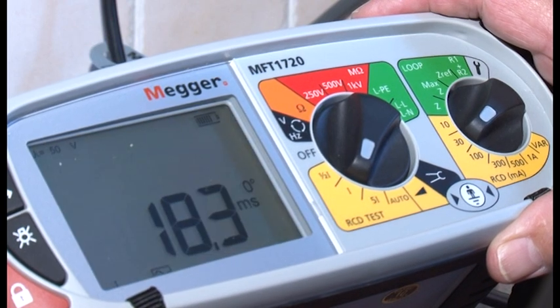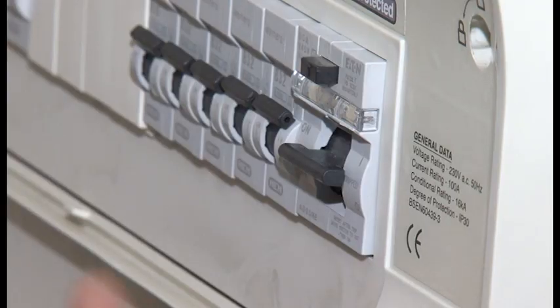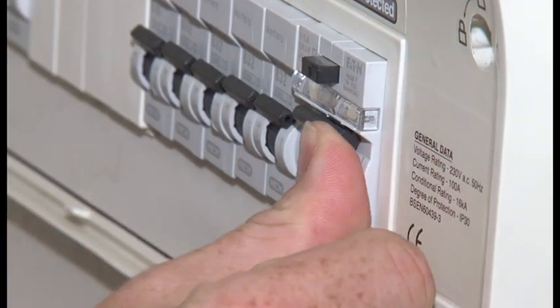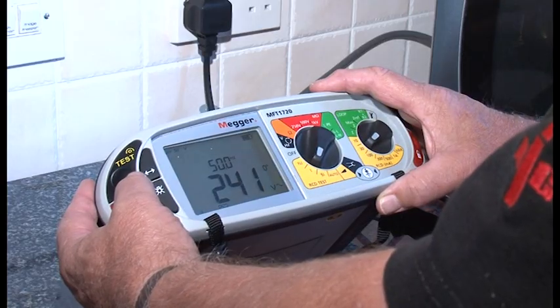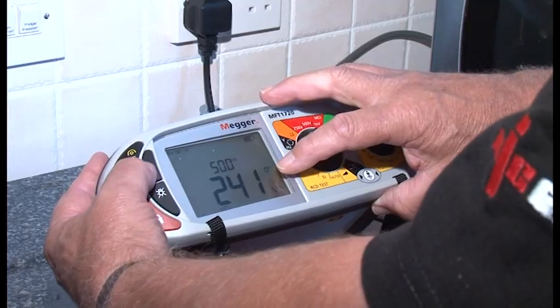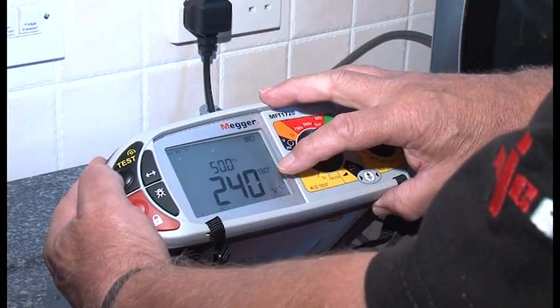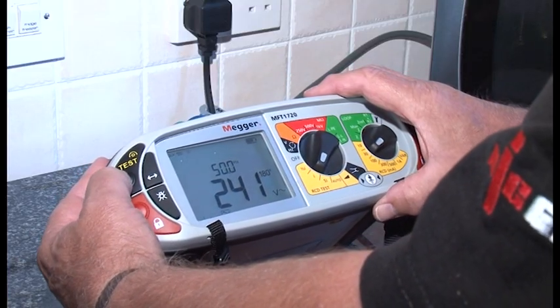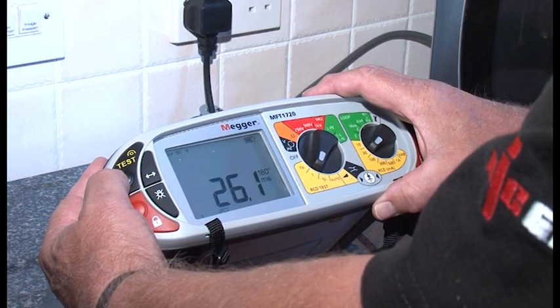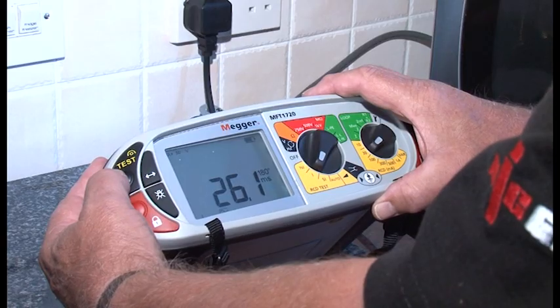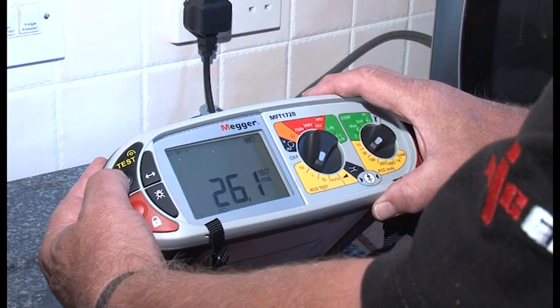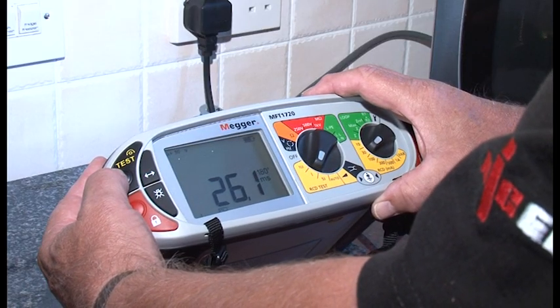Now what will happen, Dave will reset the RCD and we'll do it for the other side of the waveform. Now, if you look there, you can see I've changed the other side of the waveform. So let's repeat the test. And we've got 26.1 milliseconds. And as that's the highest reading, that will be the reading that I will record.